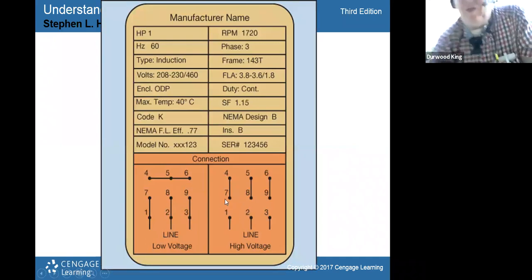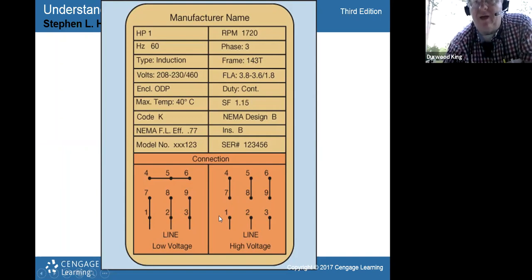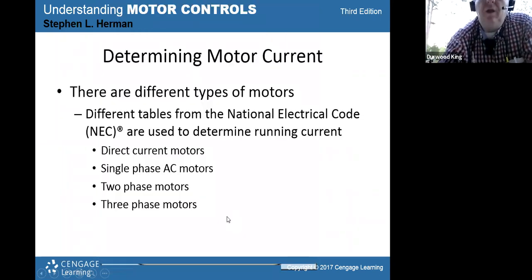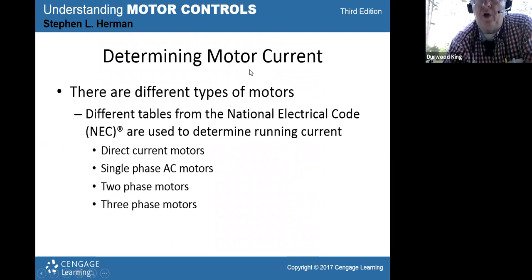now the connections. We discussed the connections. That's for low voltage connection, high voltage connection, and then determining the motor current itself. There are 3 different types of motors, and there are different tables. The tables are in the code book, the National Electric Code book, and they're in your book here. You've got DC motors, which are actually kind of phasing out. Not many people use DC motors, or direct current motors. You've got DC motors, single phase AC, 2-phase AC, and 3-phase AC.